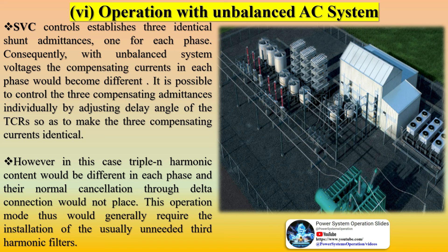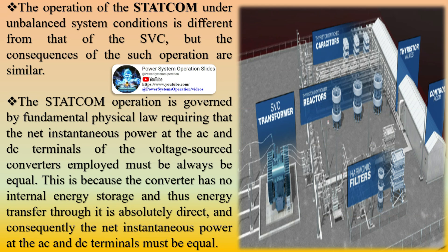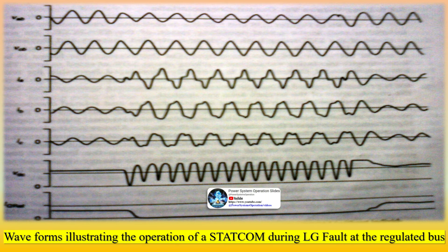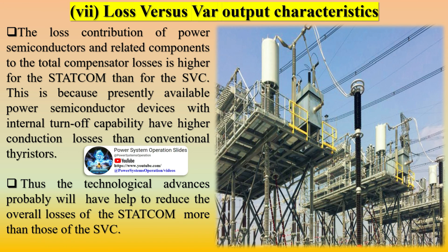The loss contribution of power semiconductors and related components to the total compensator losses is higher for the STATCOM than for the SVC. This is because presently available power semiconductor devices with internal turn-off capability have higher conduction losses than conventional thyristors. Technological advances will probably help to reduce the overall losses of the STATCOM more than those of the SVC. From the standpoint of physical installation, because the STATCOM not only controls but also internally generates the reactive output power, the large capacitor and reactor banks with their associated switchgear and protection used in conventional thyristor-controlled SVCs are not needed. This results in a significant reduction in overall size — about 30–40% — as well as installation labor and cost.